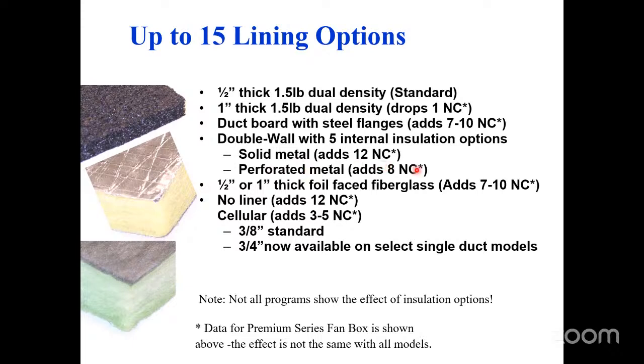The whole reason to get double wall is in order to get wipeability, cleanability. So putting holes in there doesn't help me. So that's stupid. You shouldn't do that. The foil facing adds another 7 to 10 sound penalty. You don't want that. Doing nothing obviously makes it more cleanable, but it's horrific on the sound. It's as bad as dual wall.